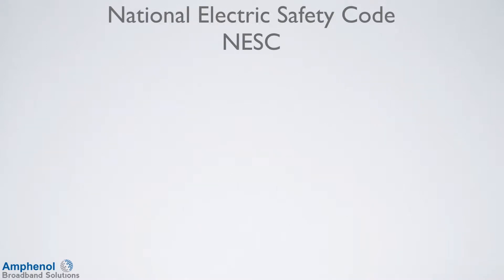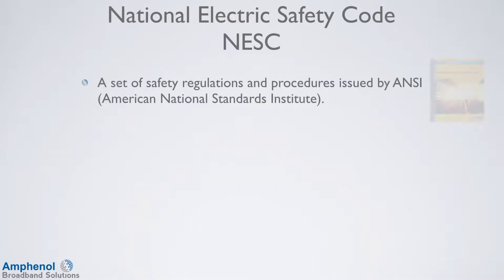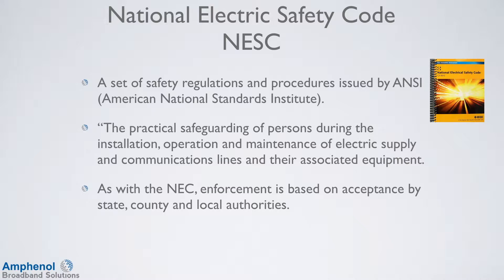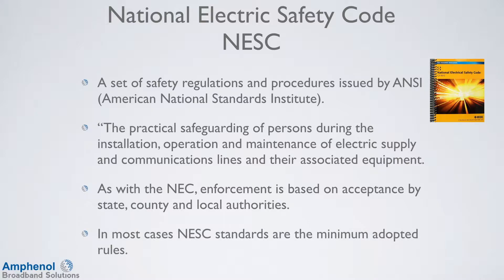The National Electrical Safety Code, NESC, is a set of safety regulations and procedures issued by ANSI, the American National Standards Institute. It sets guidelines for practical safeguarding of persons during the installation, operation, and maintenance of electrical supply and communication lines and their associated equipment. As with the NEC, they are not laws and the NESC does no enforcement. Enforcement is based on acceptance by state, county, and local authorities. In most cases, NESC standards are the minimum adopted rules.